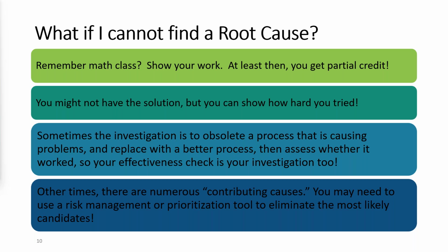At least in that instance, we couldn't find the root cause, but we showed what we had done to try to find it, which helps immensely, because when the FDA comes to inspect, they may be upset that you didn't find the root cause, but they can certainly see that you really tried your darndest.